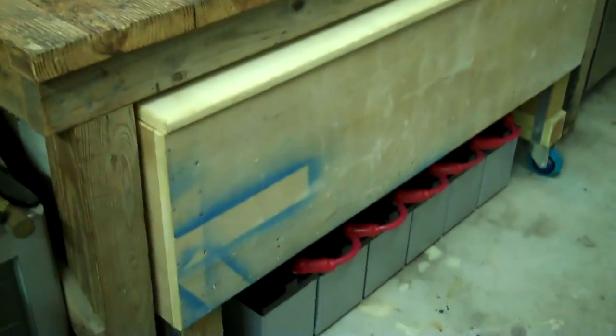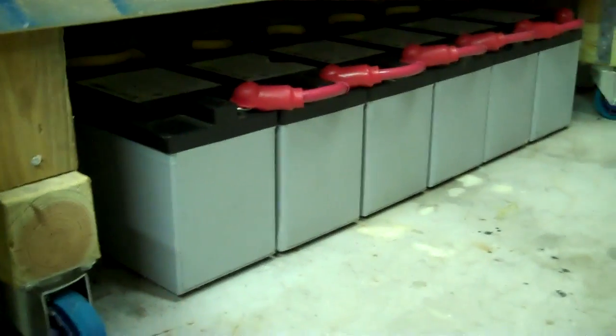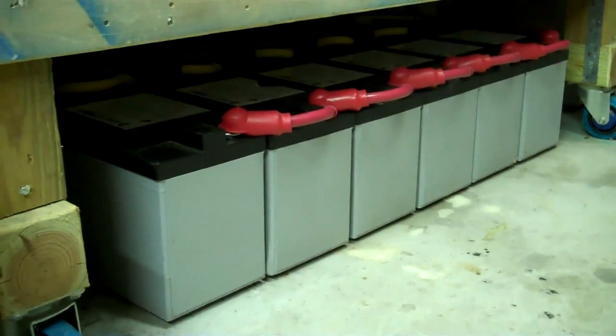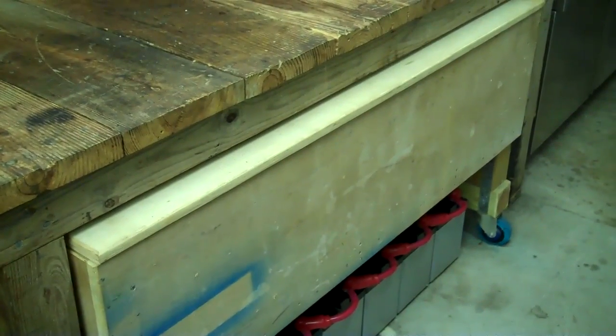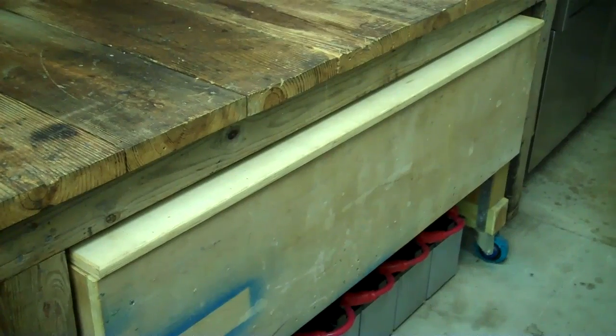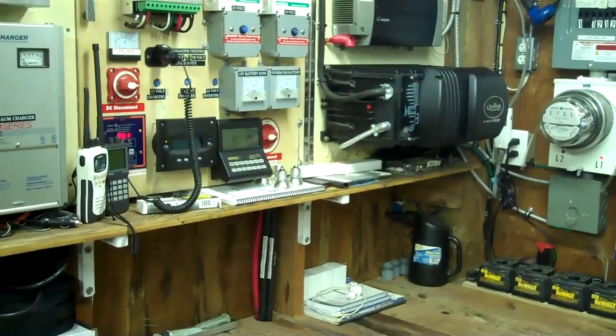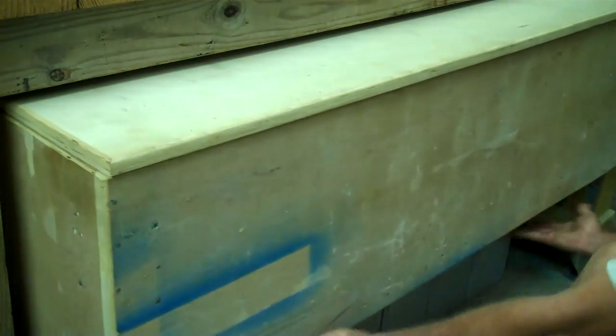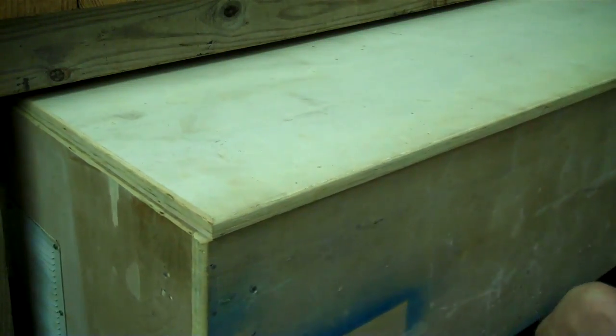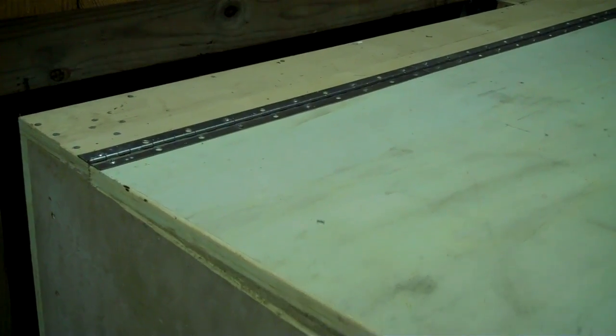This one here I'm getting ready to pull this battery bank out, and the one above. The one below is all AGMs — don't have to do much with that, just check terminals and things like that. But I'm behind schedule pulling this one out, so I'm going to yank that thing out and whatever I find, you guys will find it with me and we'll go through some of that. This is going to be about taking care of your battery banks. I hate to get behind on maintenance. This thing's heavy — this box here pretty much weighs just under a thousand pounds.